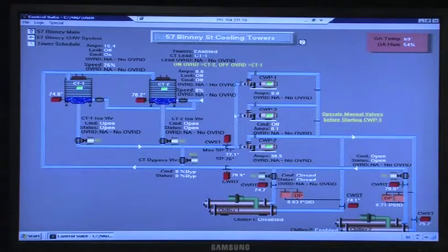So it comes down here, goes into either this pump or this pump. Either pump. The pump in the middle, up there with the condenser water pumps, is a manual pump, operating with manual valves before starting. This is not an automated pump. This is a backup with manual operation. These are automatic: one pump leads, one pump lags, and on failures they switch. If for some reason you needed to use pump number 3, you have to manually open the valves and force that pump on.